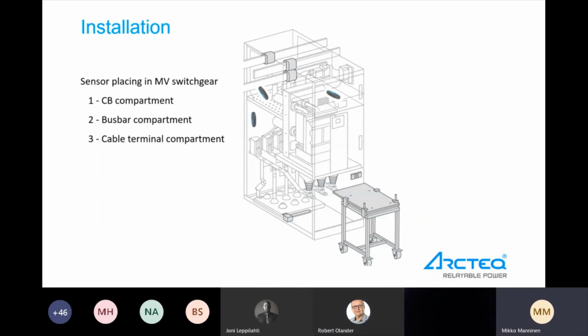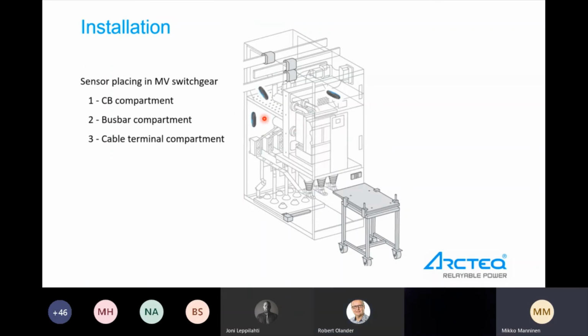This is one example for the MV switchgear. The locations are, this is just an example drawing, but you can see that there is one sensor in the cable compartment. Sometimes these cable compartments may have a segregated wall, for example, for the voltage transformer. And if there is a voltage transformer, then that also needs its own sensor.